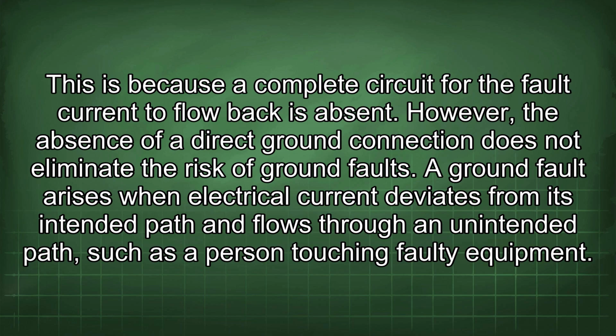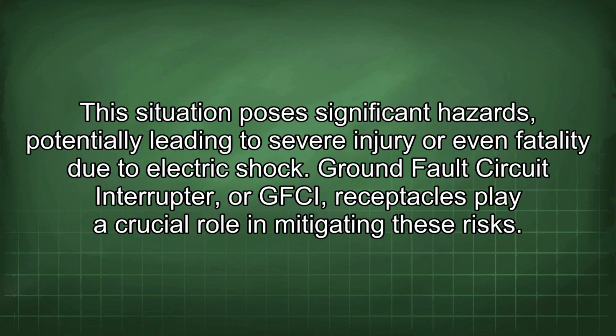However, the absence of a direct ground connection does not eliminate the risk of ground faults. A ground fault arises when electrical current deviates from its intended path and flows through an unintended path, such as a person touching faulty equipment. This situation poses significant hazards, potentially leading to severe injury or even fatality due to electric shock.